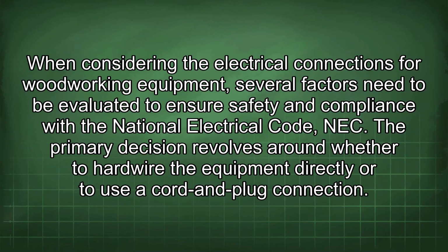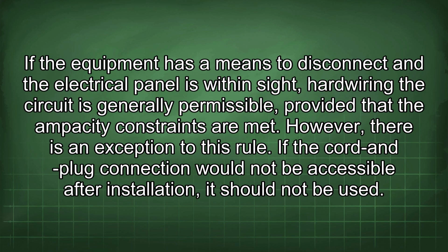When considering the electrical connections for woodworking equipment, several factors need to be evaluated to ensure safety and compliance with the National Electrical Code (NEC). The primary decision revolves around whether to hardwire the equipment directly or to use a cord and plug connection. If the equipment has a means to disconnect and the electrical panel is within sight, hardwiring the circuit is generally permissible, provided that the ampacity constraints are met. However, there is an exception to this rule.